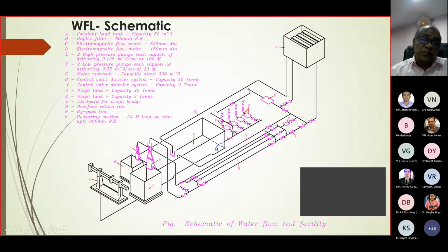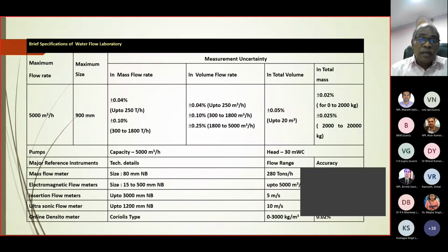With the primary calibration, this weighing system, you can achieve an accuracy of better than 0.1%. This table gives you the details. For mass flow rate, you can get better than 0.04%, that is up to 250 tons per hour. For higher range, it is better than 0.1%. Then for volume flow rate I have given here 0.04% to 0.25%. And the total volume, it is again 0.05%. This gives the capability and accuracy levels of that water flow laboratory.